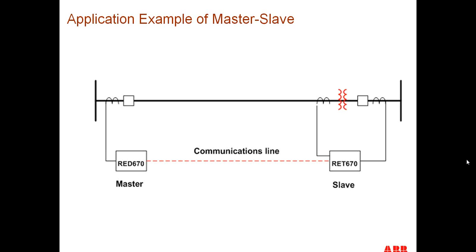Can we use permissive schemes, line differential blocking schemes, or permissive overreach? No. Permissive schemes, blocking schemes, and permissive overreaching schemes are different ways the communication logic works on a line distance relay, where you have line distance relays set to overreach the far terminal or underreach the far terminal, with a blocking or permissive scheme between the two of them. All of that kind of logic isn't needed for a current differential scheme, which just compares currents and then trips based on that. You don't have to make it that complicated.